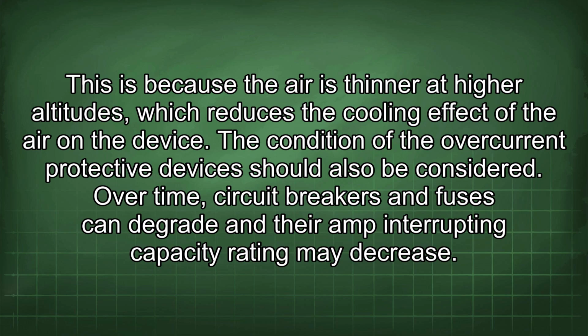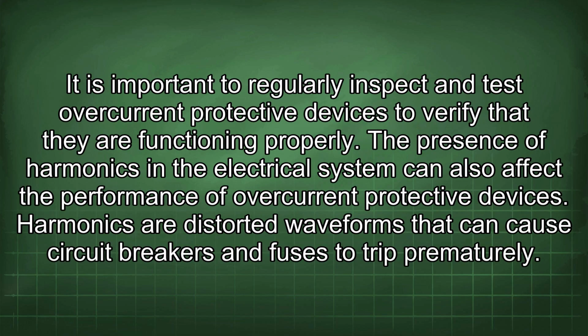This is because the air is thinner at higher altitudes, which reduces the cooling effect of the air on the device. The condition of the overcurrent protective devices should also be considered. Over time, circuit breakers and fuses can degrade and their amp interrupting capacity rating may decrease. It is important to regularly inspect and test overcurrent protective devices to verify that they are functioning properly.